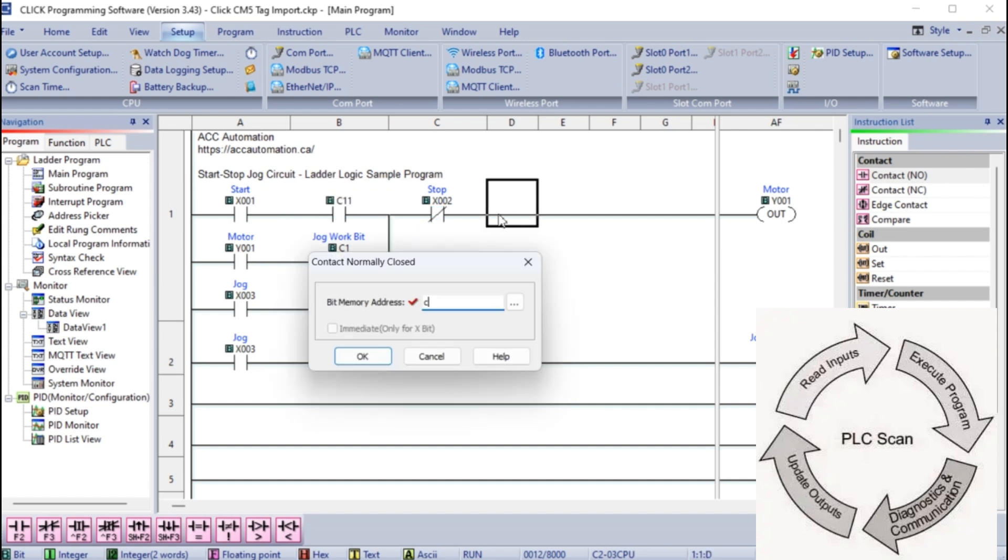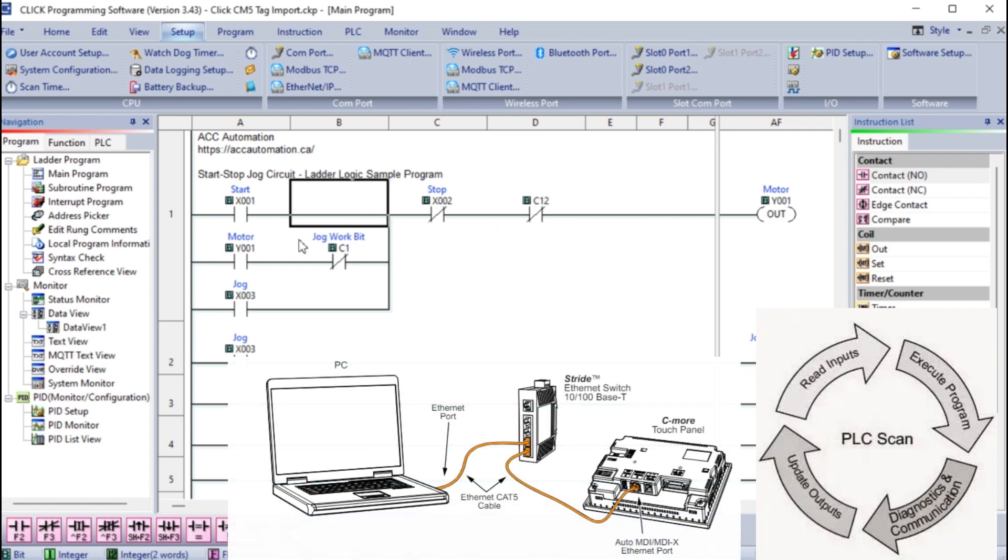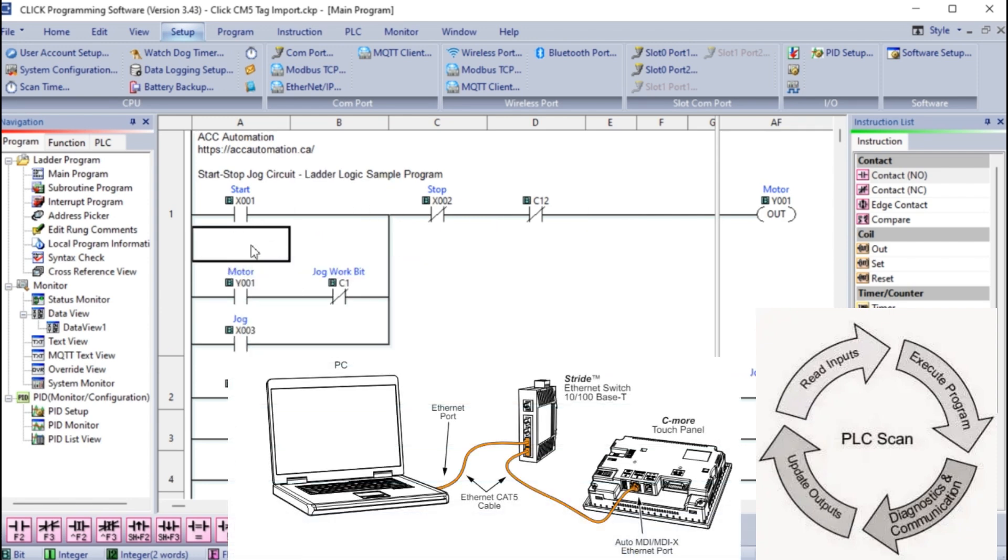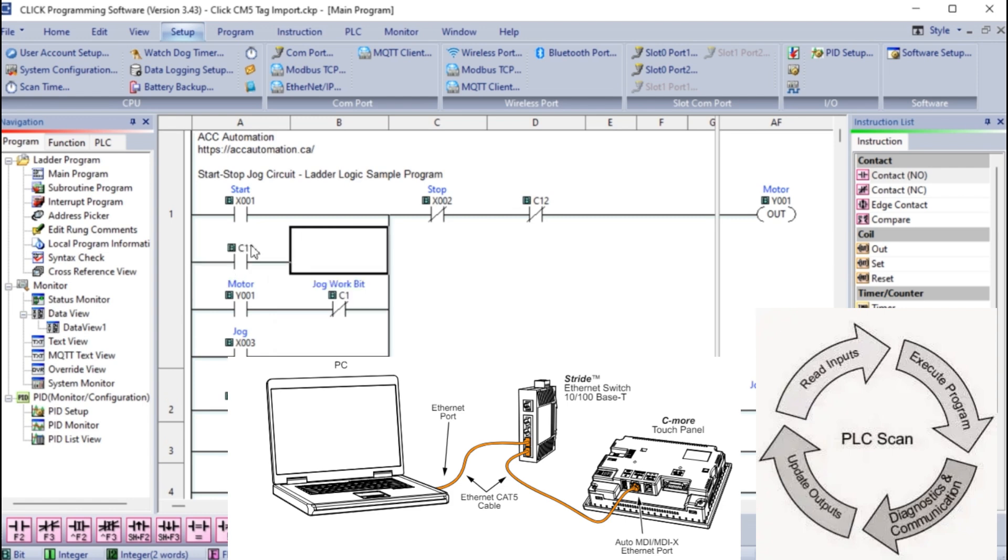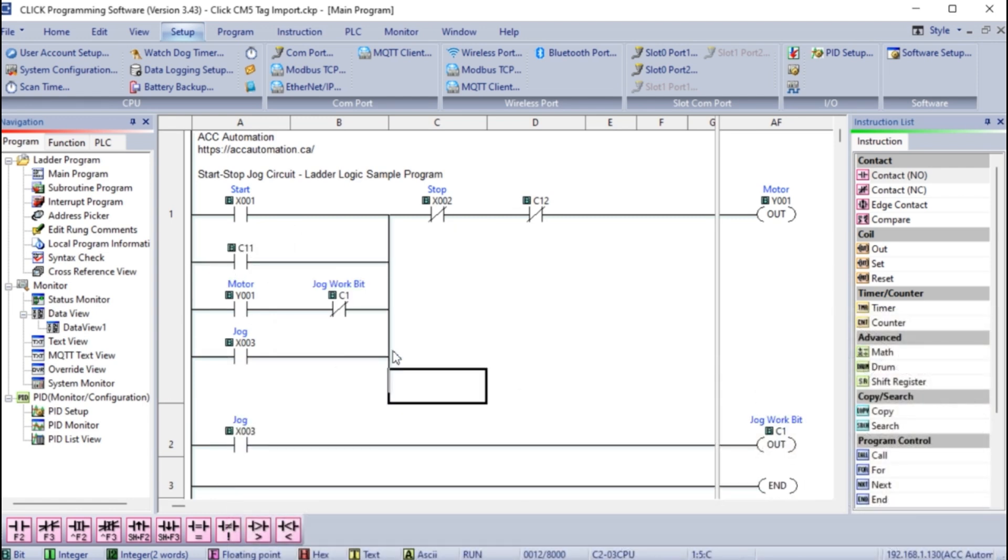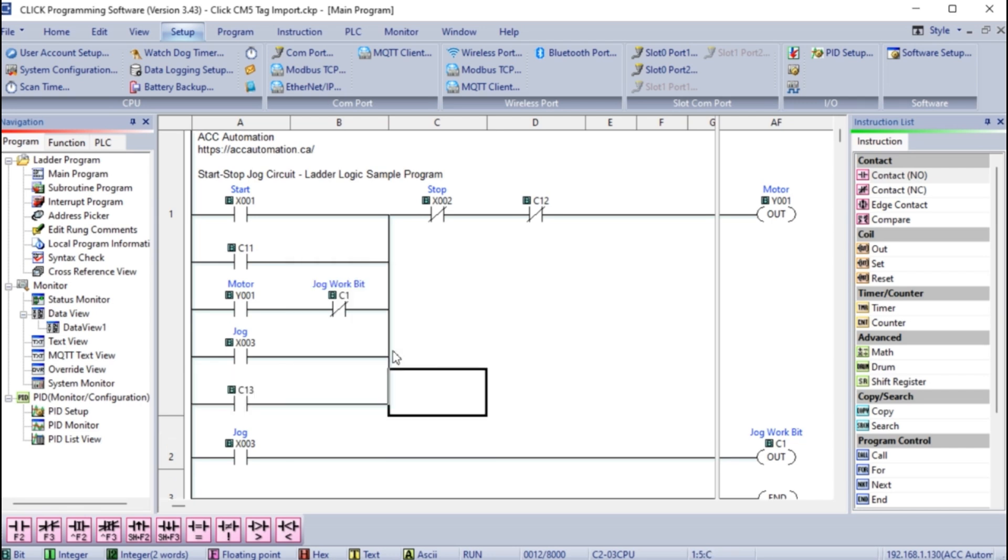This happens hundreds of times a second. The HMI will typically communicate 10 to 100 times a second, which is a slower communication. What we usually do from the HMI is to set internal bits only controlled by the HMI and use these in series or parallel to the existing contacts in the PLC.